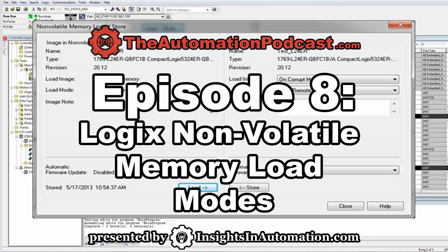So on an older ControlLogix or CompactLogix that has a battery, we simply just remove the battery and turn off power. On the newer ControlLogix and CompactLogix, we have to hold down that default comms button as we power the processor on to erase the processor's memory. So okay, let's go ahead and do our test. First, remove your non-volatile memory card. Then, on your controller, either remove the battery and cycle power, or press down on the default comms button and cycle power.